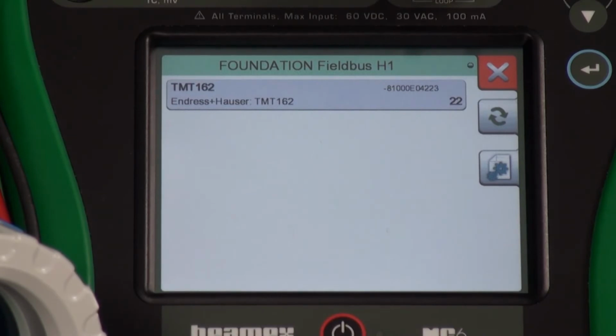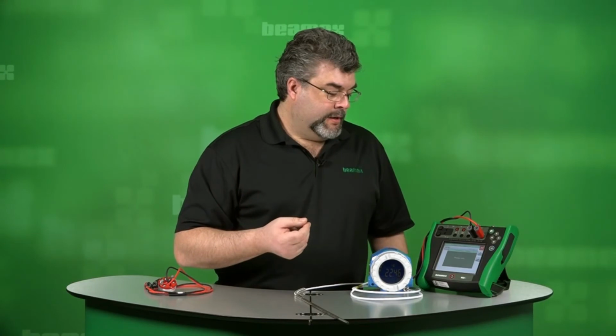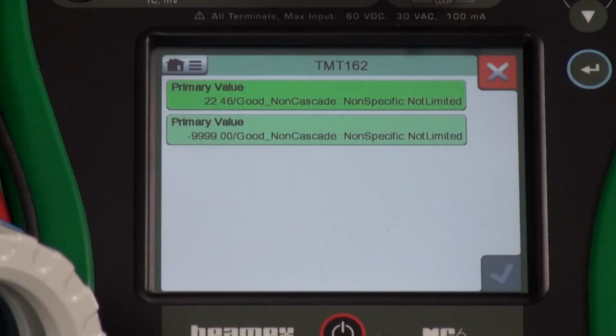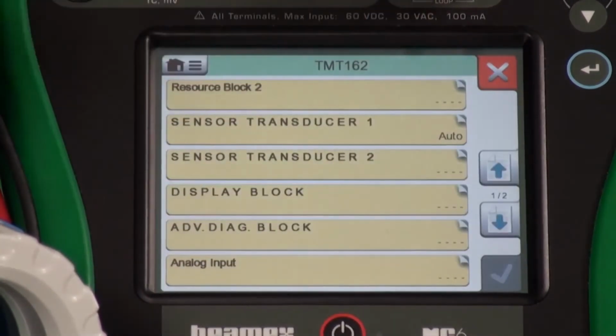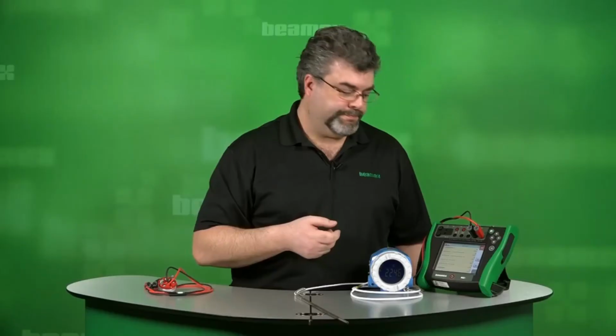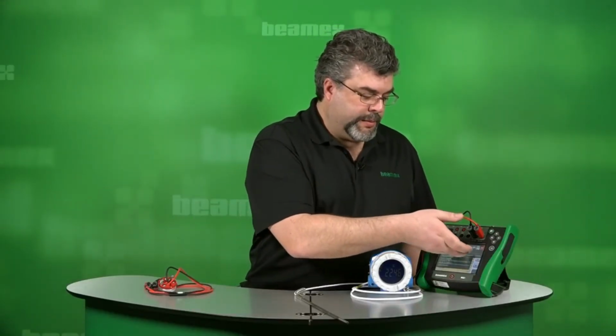It's found our tag, TMT162. When we select it, it will show you the file structure of the DD or the device descriptor. One thing to note: depending on if you want to re-range the transmitter, change different values, or do trimming functions, the names of each of the categories will vary based on manufacturer. I'm looking right now in the show measurable variables. If I wanted to see everything, I could just go to show all, and this is the standard structure that you would see. Let me go back to showing the measurable variables.